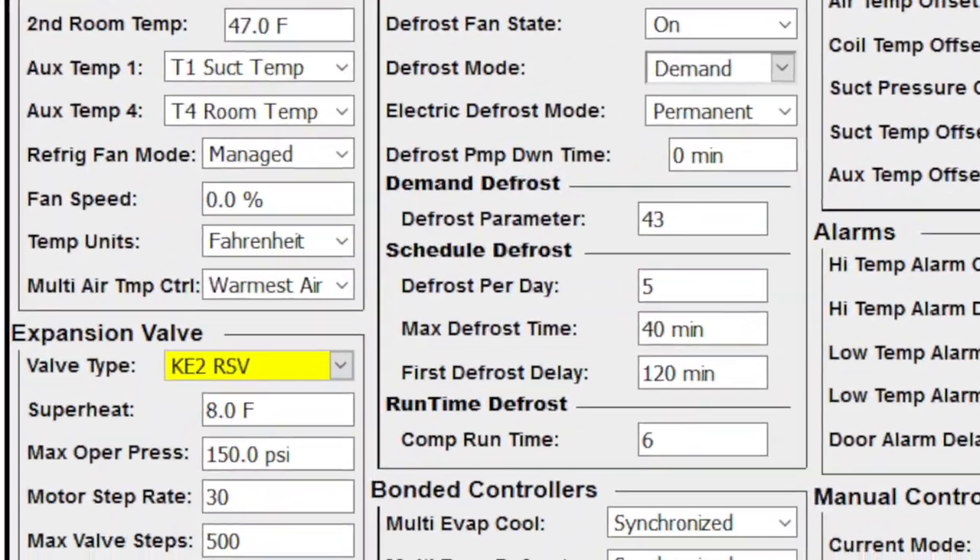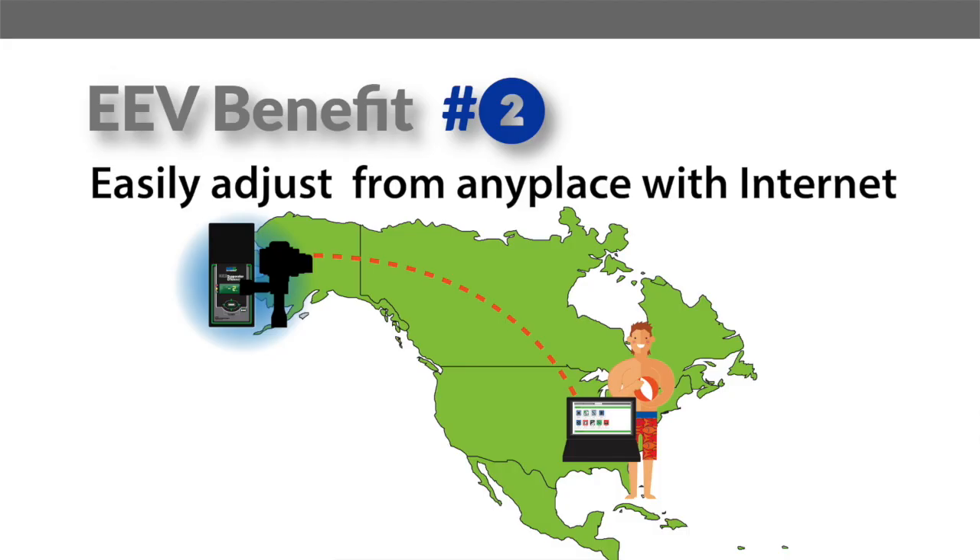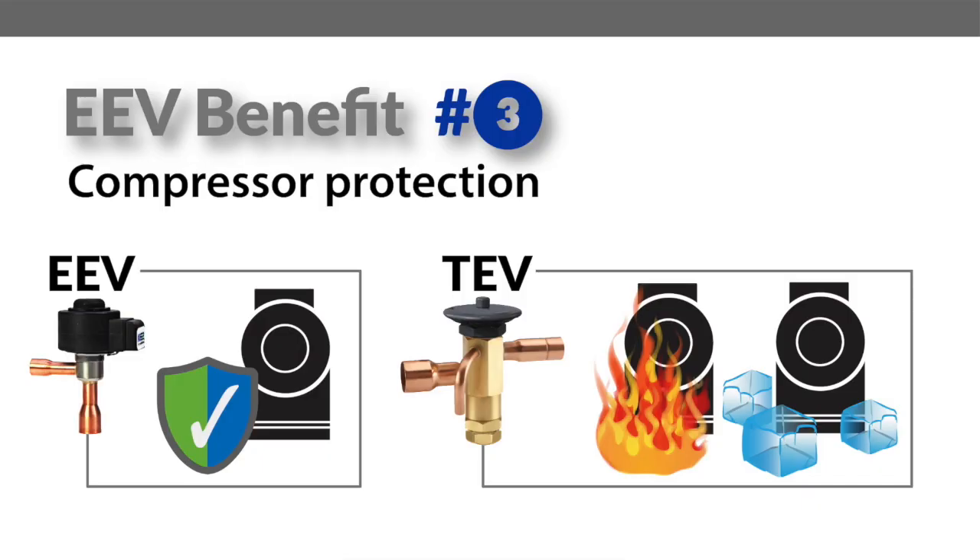If you ever want to adjust the target superheat, you can do this easily through the controller — your smartphone, tablet, or PC — on-site or remotely. The KE2 controller also drives the valve completely closed during low superheat. This means if the fans go out, the coil gets iced up, or there's a low superheat condition for whatever reason, the controller will do its best to protect the compressor. This is something a TEV cannot do.